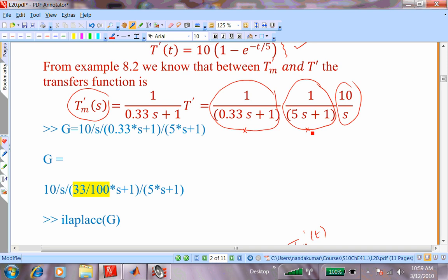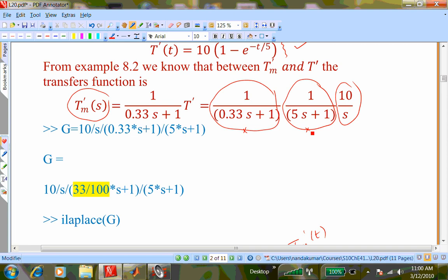Mathematically, yes, but okay, now you are an instrumentation engineer. You are designing the thermocouple. Can you do something to the thermocouple so that it responds instantaneously? It measures, it senses T, and it sends out the signal T at the same time, not a different signal. What would you have to do to achieve that? You are now the designer of the thermocouple, not a purchaser. What would be your goal to achieve that? That's what I'm looking for. Reduce your tau m, the time constant.